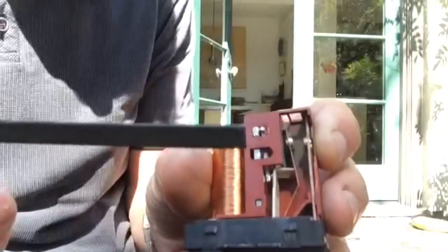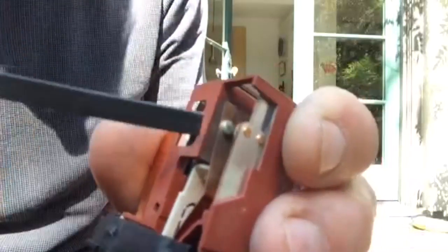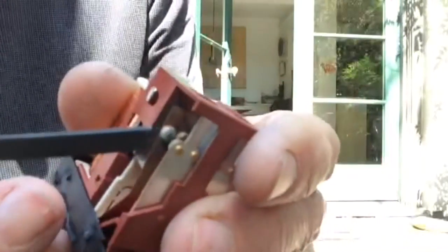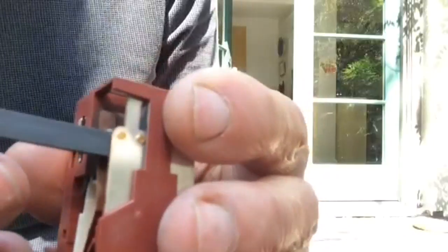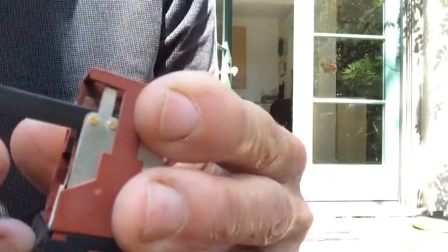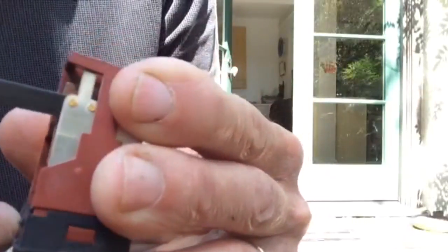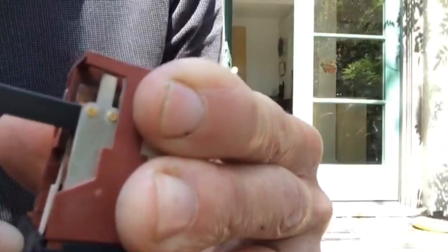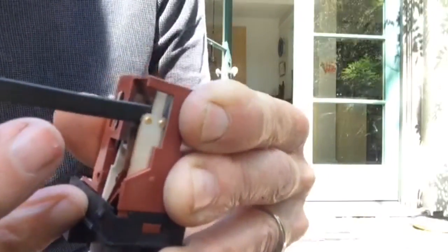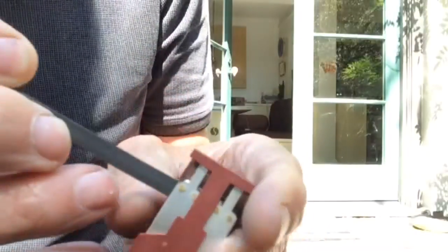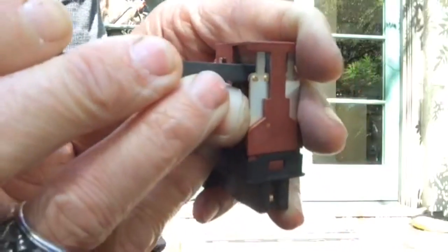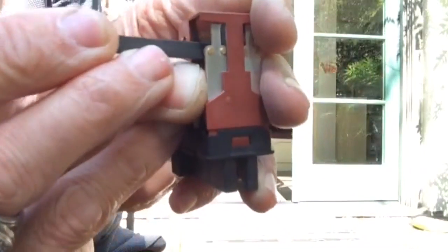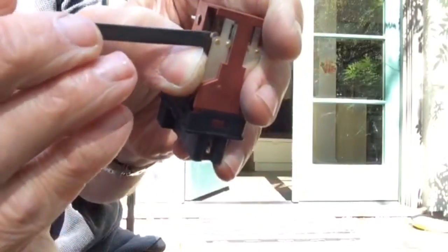Like the points on an old distributor on a car, we just use a flat file. And we can see that these points are kind of pitted and dark colored. We have a lot of carbonation. And that's because every time the heater turns on, these relays close to allow energy to flow to the heater. And there's a little spark that's created. And that spark causes oxidation or a little bit of carbon buildup.